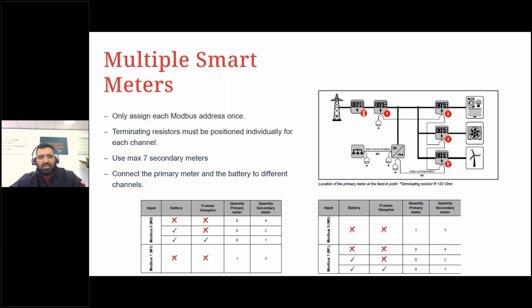Another thing to keep in mind is to make sure that each meter has a unique Modbus address. Most meters come with the address number 1, so you can't have four number 1s in the same line. You'd have to number them as 1, 2, 3, and 4, for example.